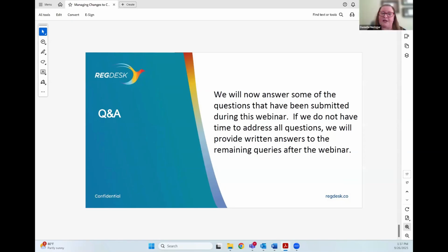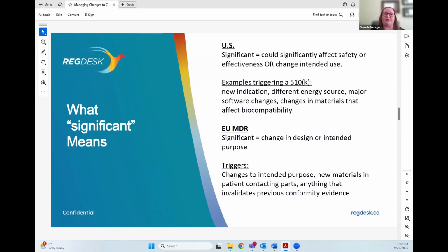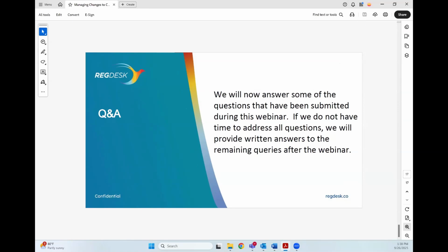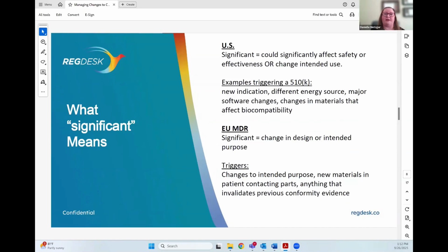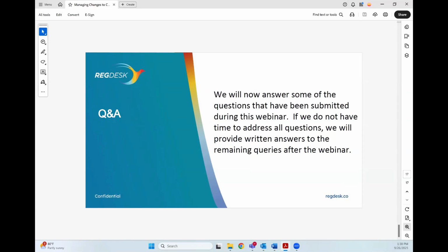All right, another question is, do all changes require prior approval? I'll take that one on. Actually, no, they don't. Some jurisdictions do allow for what's called non-reportable changes, where we do a letter to file in the FDA, or there are amendments that we do in other regions. But what's important to know is that even though we can classify something as a non-reportable change, it still must be documented under the QMS and available for audit.